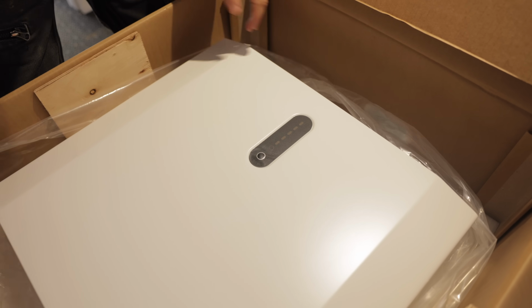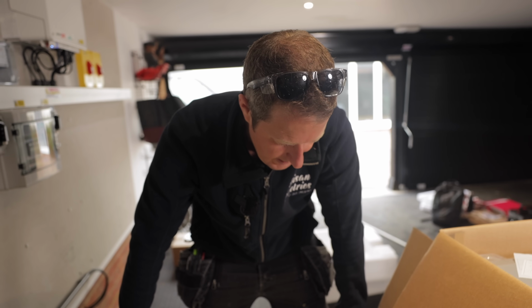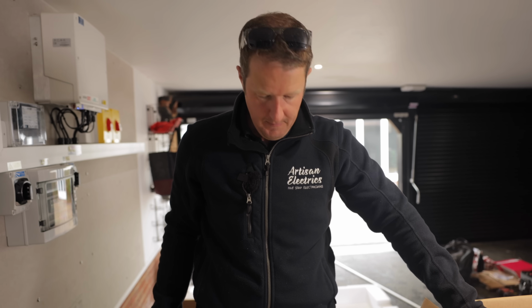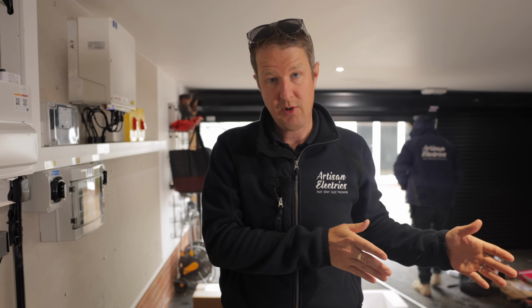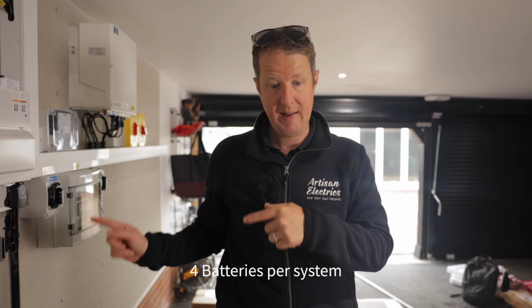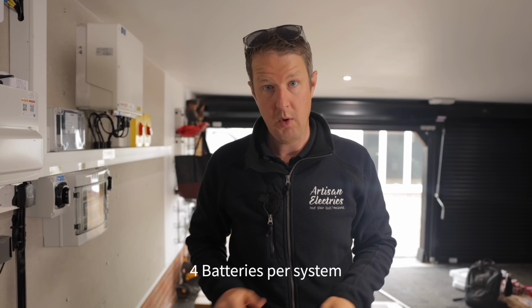Each of these battery modules is 5 kilowatt hours, and you can stack up to 4 batteries on one inverter in 2 stacks. So you can have the inverter and 2 batteries adding up to 10 kilowatt hours, then another stack of 2 batteries next to it for a total of 20 kilowatt hours, which is what we're going to do here. That's the maximum size system you can have on one phase.